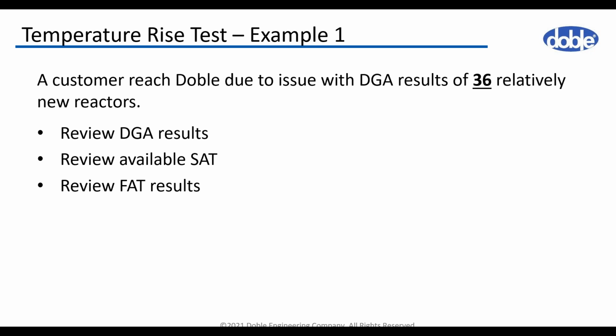I would like to show you some practical examples from our real work in the field, where we found some issue. We have a customer who asked us to check his DGA results for 36 shunt reactors, which were relatively new. And the reason was that the customer found the DGA really suspicious. So we insisted also to have a look at the field test results and also the available factory test results.